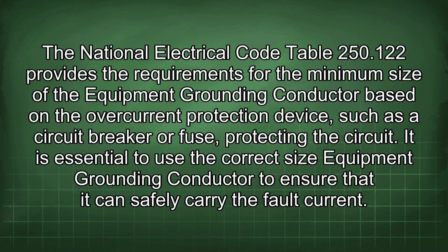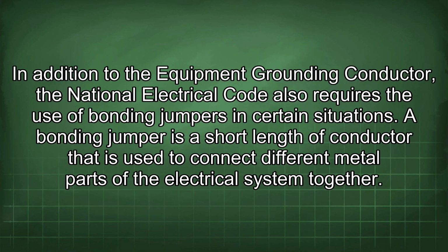250.122 provides the requirements for the minimum size of the equipment grounding conductor based on the overcurrent protection device, such as the circuit breaker or fuse protecting the circuit. It is essential to use the correct size equipment grounding conductor to ensure that it can safely carry the fault current.